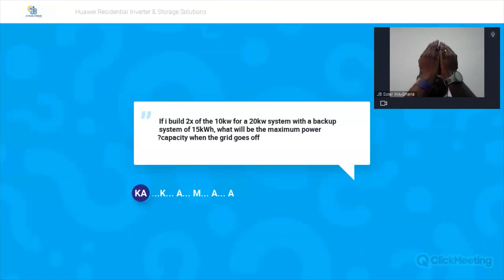So take note, the maximum discharge from the battery solution is 5 kilowatts. The maximum discharge when the backup box comes into play is 3.3 kilowatts. Please take note, these points are very, very crucial here.